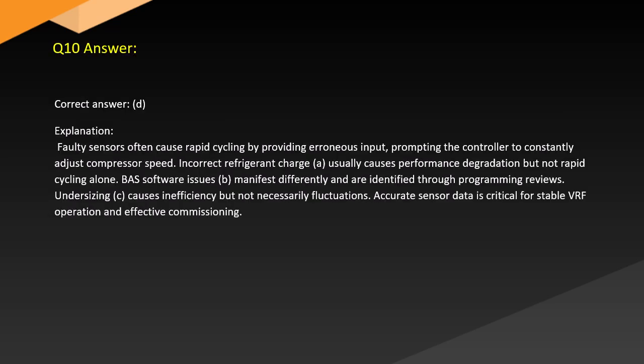Answer. Correct answer: D. Explanation. Faulty sensors often cause rapid cycling by providing erroneous input, prompting the controller to constantly adjust compressor speed. Incorrect refrigerant charge usually causes performance degradation but not rapid cycling alone. BAS software issues (B) manifest differently and are identified through programming reviews. Undersizing (C) causes inefficiency but not necessarily fluctuations. Accurate sensor data is critical for stable VRF operation and effective commissioning.